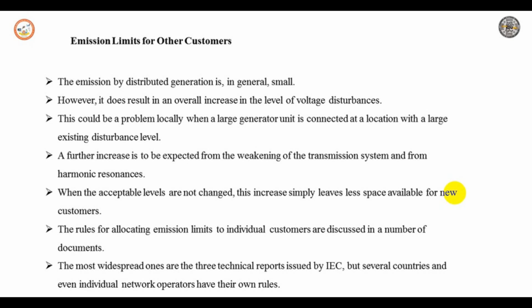This is called the planning level. Next, the planning level is compared with the existing level, that is, before the connection of new customers. The difference between the existing level and the planning level is the permitted increase due to new customers. Using some kind of allocation algorithm, this emission limit in terms of voltage is determined. Keeping the planning level unchanged will result in reduced emission allocation for new customers. These new customers may actually be a distributed generator or a wind park. When the existing level comes closer to the planning level or even exceeds it, connecting a new installation could become difficult and expensive.